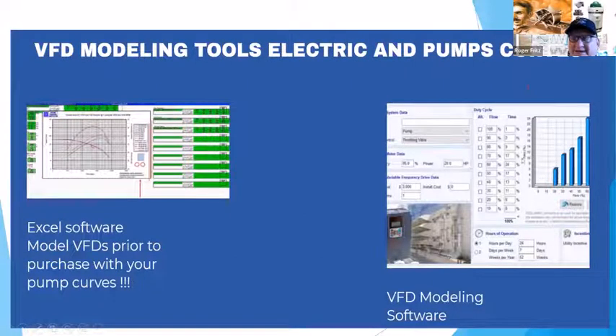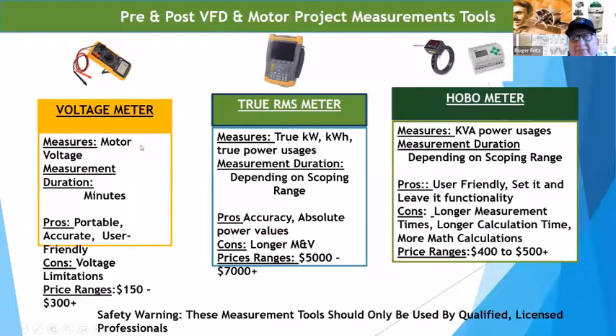But the problem is that this doesn't take into consideration the pump curve. So you need to also look at the effects of the pump curve. And I think ultimately, as time goes on, these two will be brought together. Again, then the proper metering tools, your straight voltage measurements, that are out there, portable, easy to use, fairly cost effective.